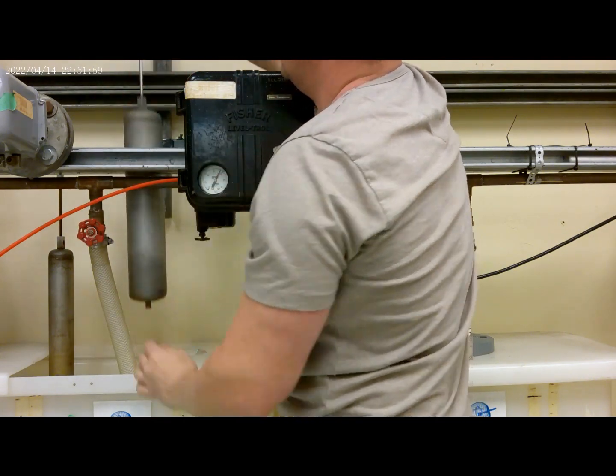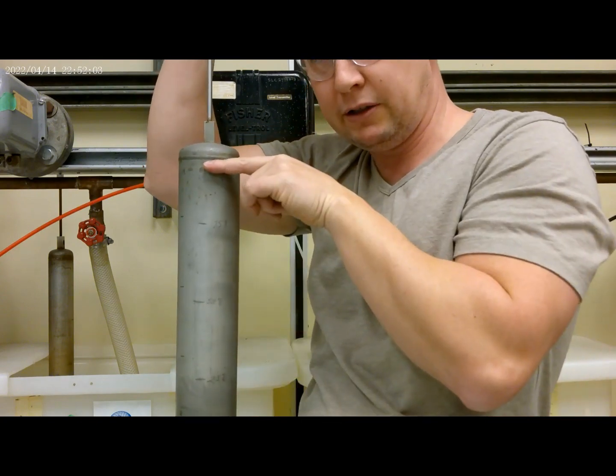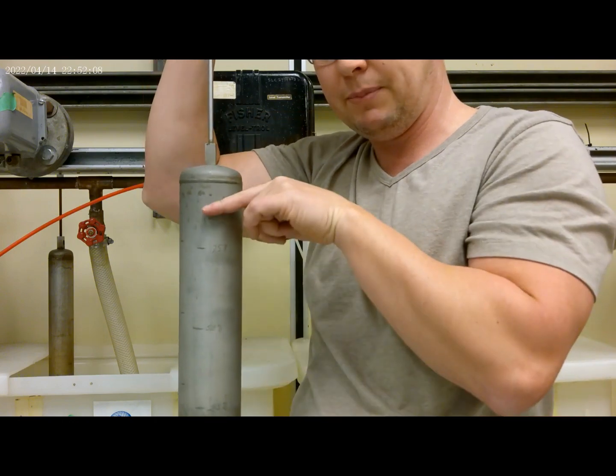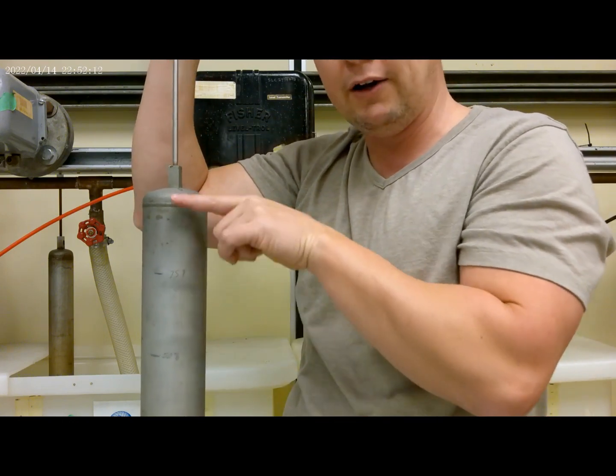Now, our displacer is right here. We are going to go the entire length of the displacer. When the water level is down here, we'll get 3 psi out. When it's up here, we'll get 15. It'll go 3, 6, 9, 12, and 15.